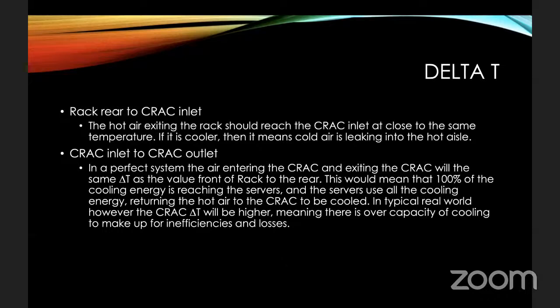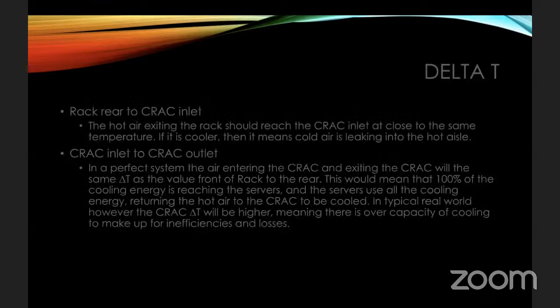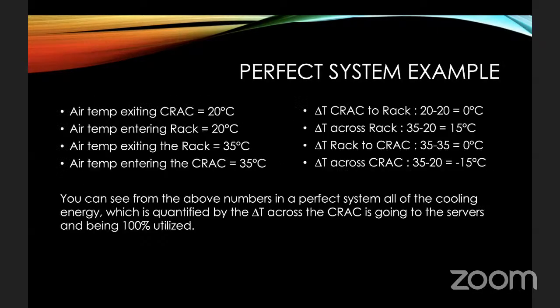And the last delta T to look at is the CRAC inlet to the CRAC outlet. So in a perfect system, the air entering the CRAC and exiting the CRAC will have the same delta T as the front to rear. This would mean that 100% of the cooling energy is being used. In a typical real world, however, the CRAC delta T will be higher, meaning that you've got an overcapacity, which is usually to make up for inefficiencies and losses. And to explain this more clearly, I'm going to show you an example of the calculation of a perfect system.